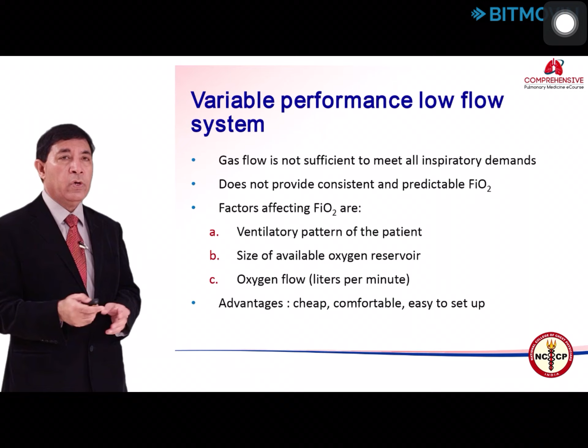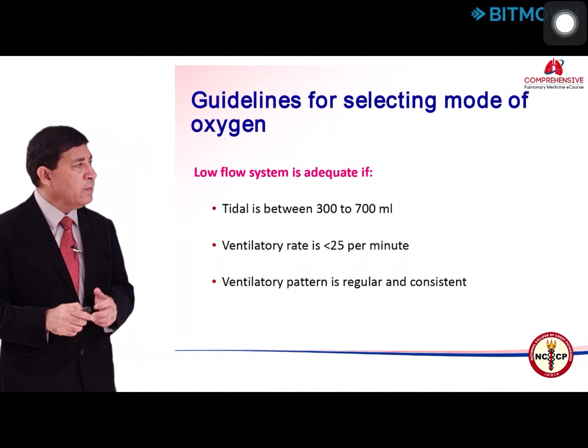So, low flow systems are adequate if the tidal volume is between 300 to 700 ml, if the rate is less than 25 per minute and the ventilatory pattern is regular and consistent. And it should be used in situations where a constant FiO2 is not required.